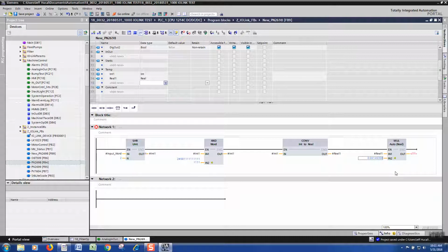And what is this going to do for me? It's going to scale this input number to inches of H2O. Oh, okay. Is that all this does is H2O right now? And then you can just change this setting later? Yeah, you can change it later, but in order for this scheme to work, it's always got to be inches of H2O. Once you set all this stuff up, then you can change this, and it does some further math to get it to where you want. Right. Okay. All right, so make that real 1 on the output.